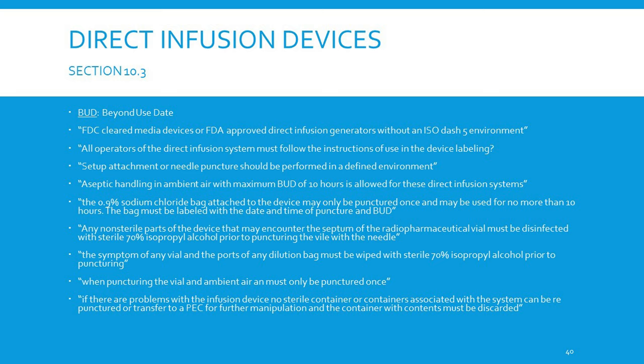Any non-sterile parts of the device that may encounter the septum of the radiopharmaceutical vial must be disinfected with sterile 70% isopropyl alcohol prior to puncturing the vial. The septum of any vial or dilution bag must be wiped with sterile 70% isopropyl alcohol prior to puncturing. When puncturing the vial in ambient air, it must only be punctured once. If there are problems with the infusion device, no sterile container associated with the system may be re-punctured — it must be transferred to a PEC for further manipulation or discarded.